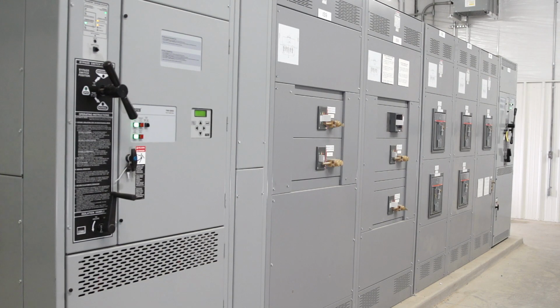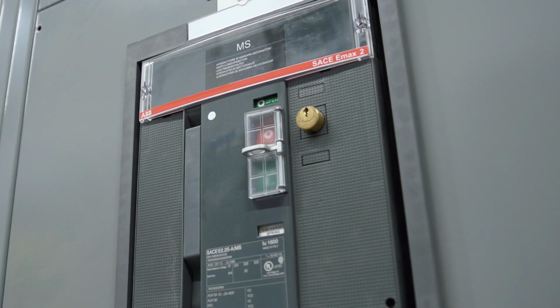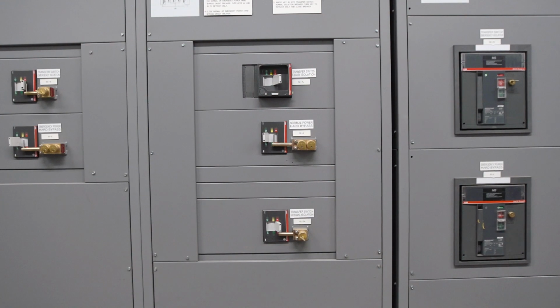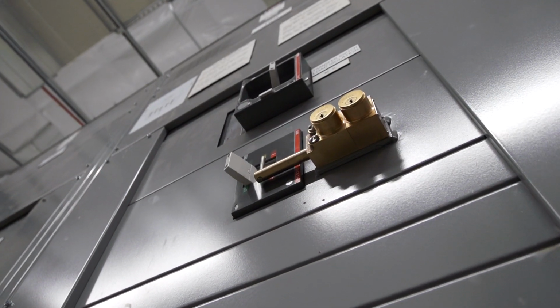The requirements for justifying this task are that the equipment has been properly installed and maintained, the doors are on, covers are closed, and there are no signs of impending failure. Equipment must be used for its OEM intended purpose, and the doors and covers must be secured. Remember, maintaining production is not an adequate reason to perform energized work. If you take one sentence away from this entire training, let it be this: always create an electrically safe work condition first, and if not possible, use insulated tools and wear PPE.